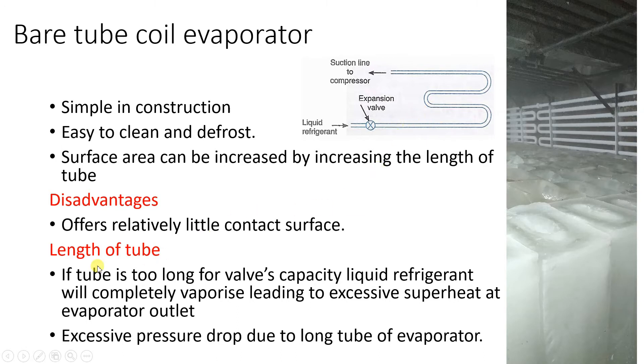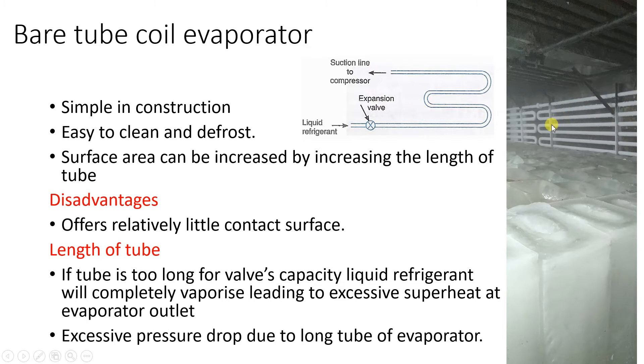Since this is natural convection type, the tube length must be large, which is also a disadvantage. The valve capacity means liquid refrigerant may completely vaporize before the end of the tube, leading to excessive superheat at the evaporator outlet. Additional disadvantages include increased refrigerant inventory, higher cost, and larger pressure drop due to the long tube. It also offers relatively little contact surface area between air and the evaporator tube, since there are no fins on this bare tube coil.